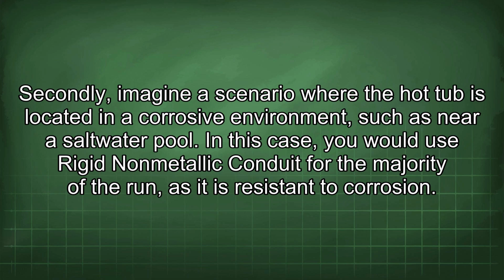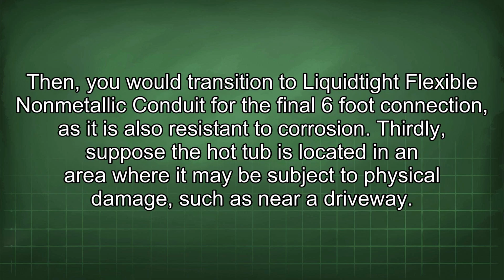Secondly, imagine a scenario where the hot tub is located in a corrosive environment such as near a saltwater pool. In this case, you would use rigid non-metallic conduit for the majority of the run, as it is resistant to corrosion.